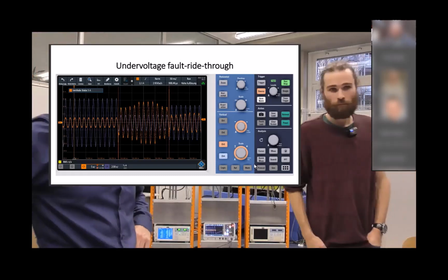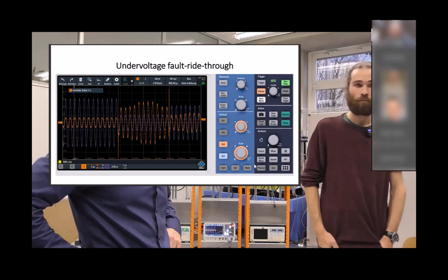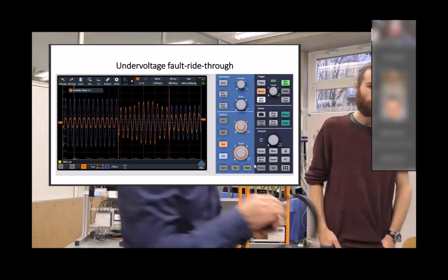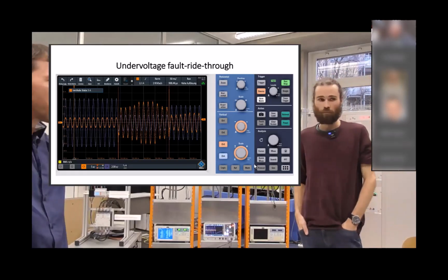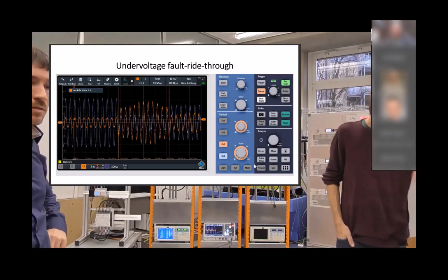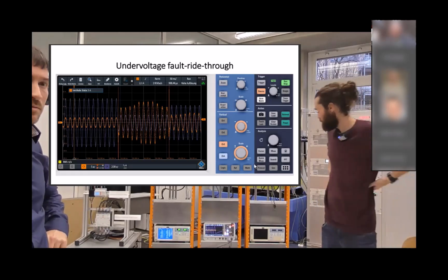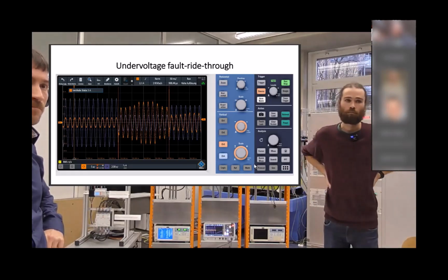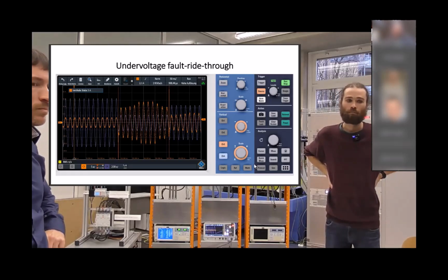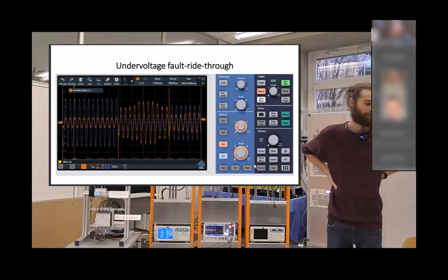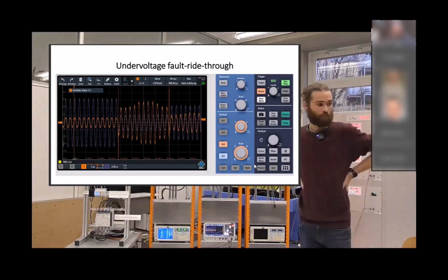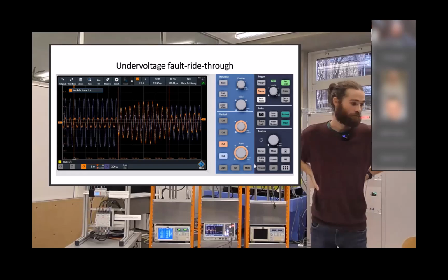It's a general behavior, as Theo said. Now that you can see the low level of voltage, but from the DC side, the power supply gives the constant active power. So in order to keep such active power, the PCE shall raise the current to keep the input active power. So matching the low voltage level, the current level goes up. This is a very basic phenomenon of the current source inverter.